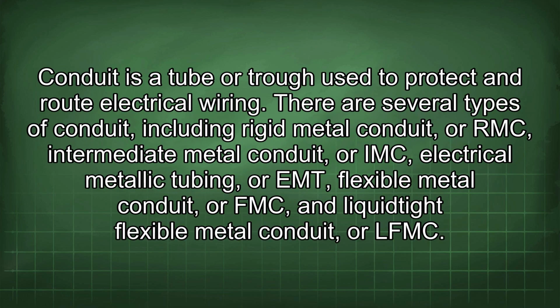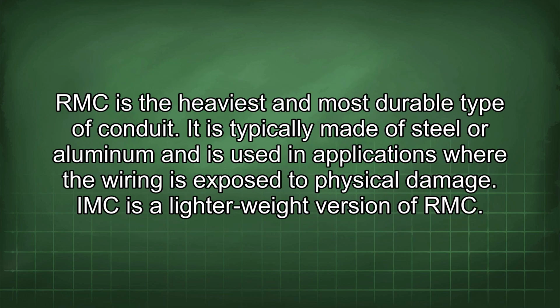Conduit is a tube or trough used to protect and route electrical wiring. There are several types of conduit, including rigid metal conduit, or RMC, intermediate metal conduit, or IMC, electrical metallic tubing, or EMT, flexible metal conduit, or FMC, and liquid-tight flexible metal conduit, or LFMC. RMC is the heaviest and most durable type of conduit.